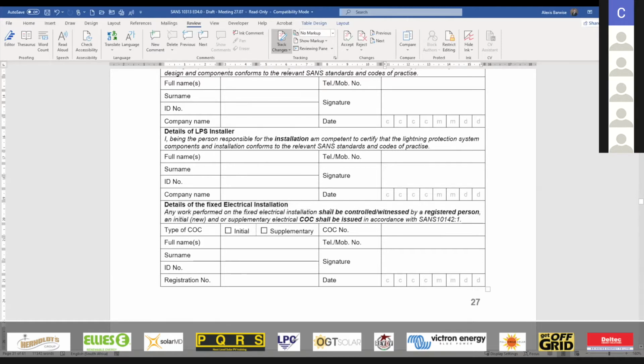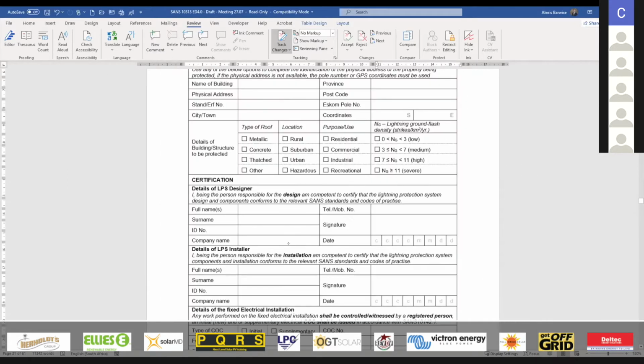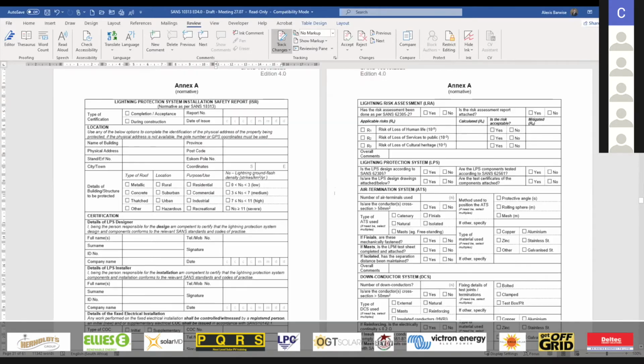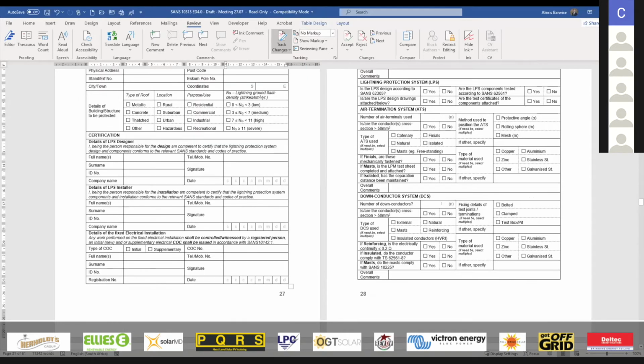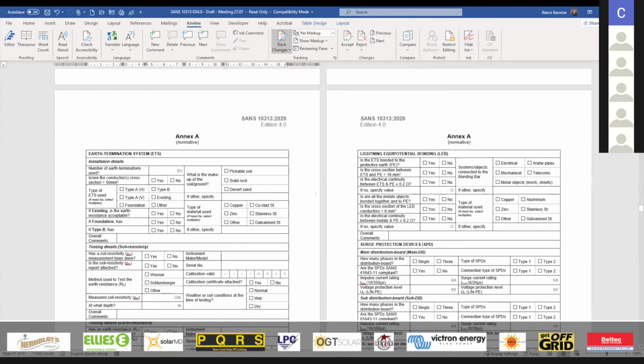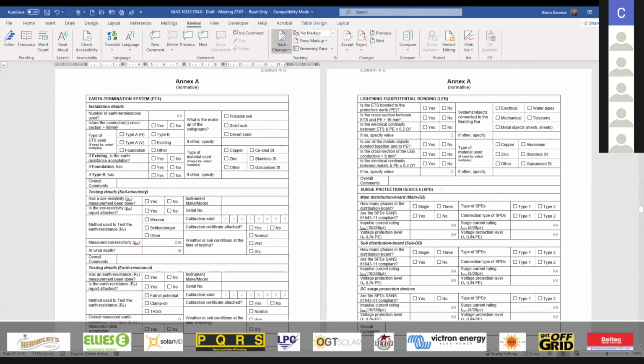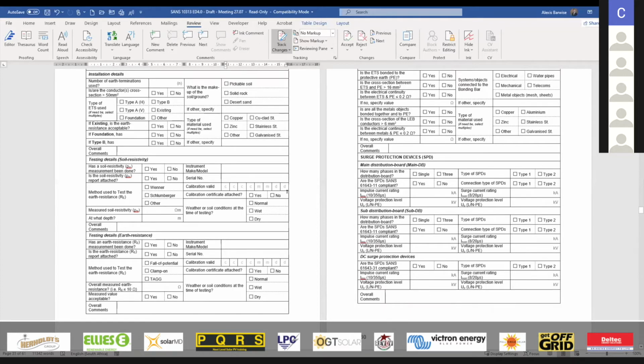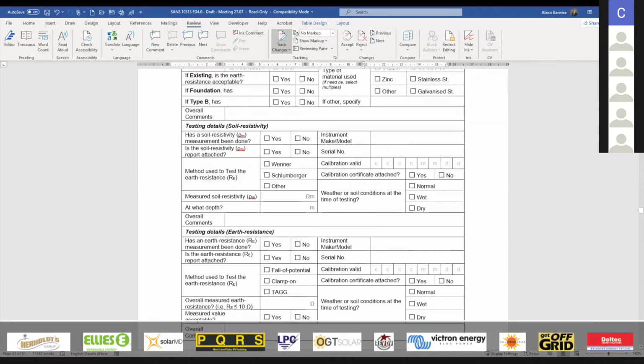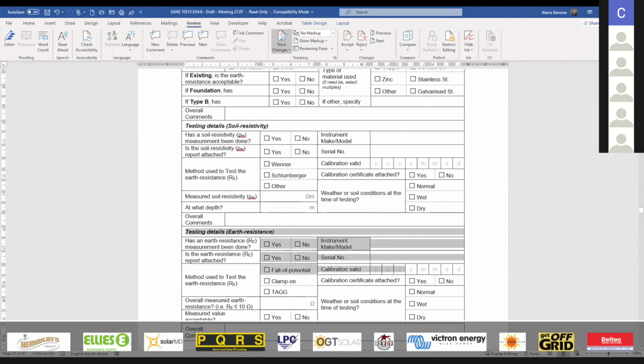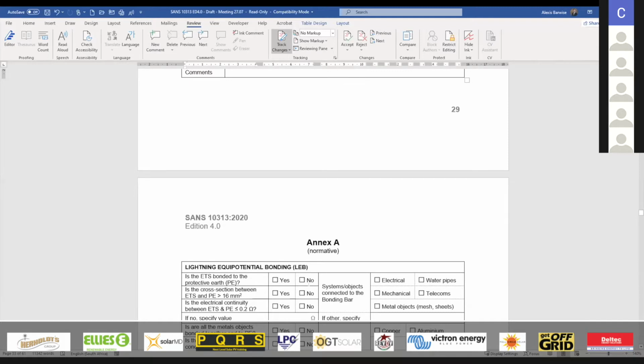This is the safety report that you would then attach to your COCs. There are multiple other pages to it attesting to the details - filling in what size of surge protection you used, what size of conductor was used as the bonding conductor, whether you did the earthing test, what the earthing test results were, and whether you had a calibrated instrument. You can go through this when the standard is shared with you.